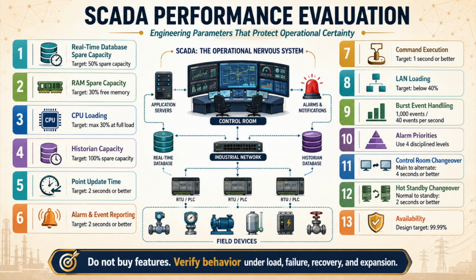A minimum 50% spare real-time database capacity should be treated as a practical design margin, because future stations, diagnostic points, calculated tags, cybersecurity monitoring tags, communication quality tags, redundant tags, virtual tags, interface tags, and analytics tags will always appear later. And if the database has no reserve, every expansion becomes a negotiation. Every diagnostic improvement becomes a burden, and every cybersecurity addition becomes a compromise. A point is never just a point.